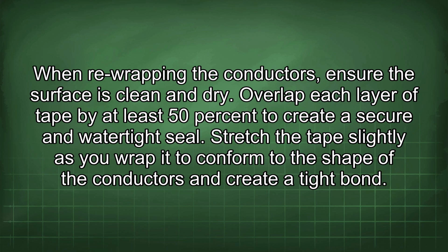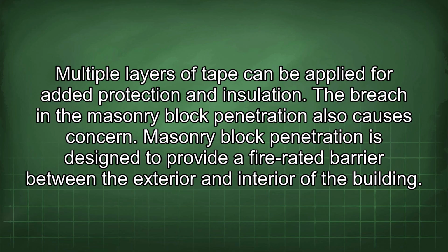When rewrapping the conductors, ensure the surface is clean and dry. Overlap each layer of tape by at least 50% to create a secure and watertight seal. Stretch the tape slightly as you wrap it to conform to the shape of the conductors and create a tight bond. Multiple layers of tape can be applied for added protection and insulation.